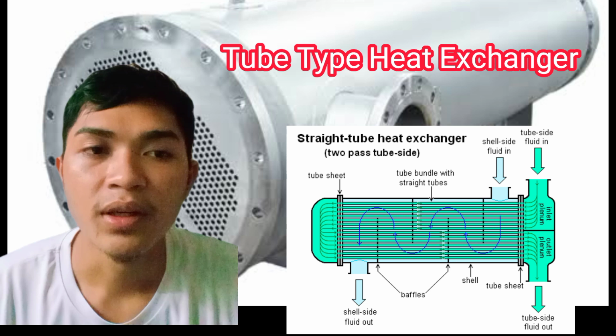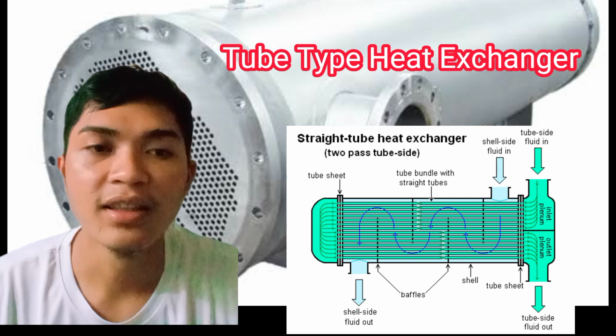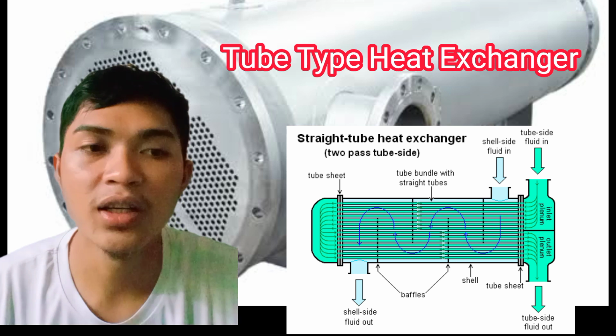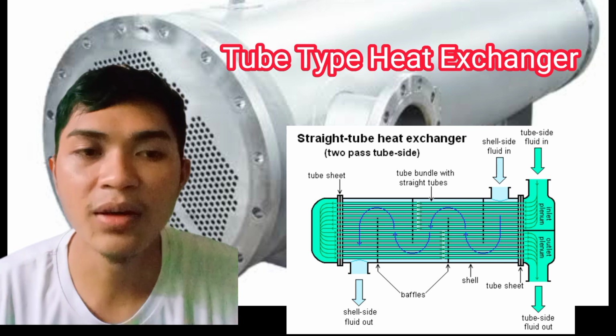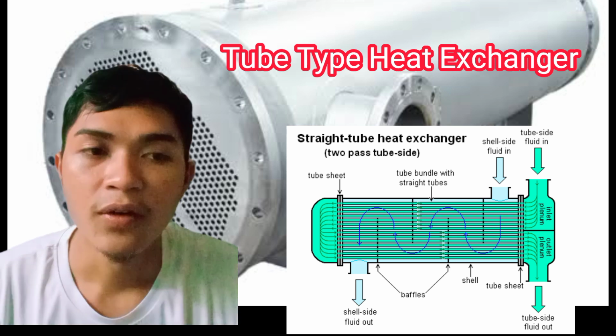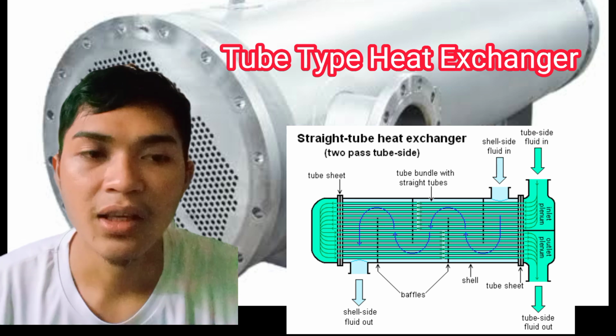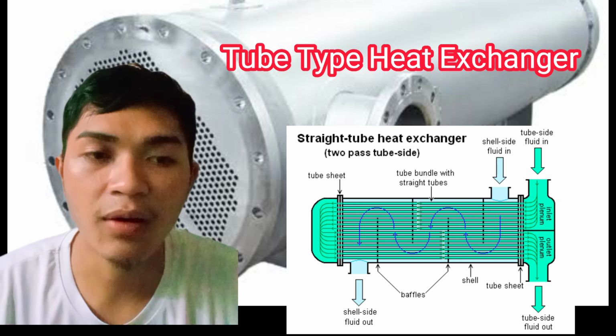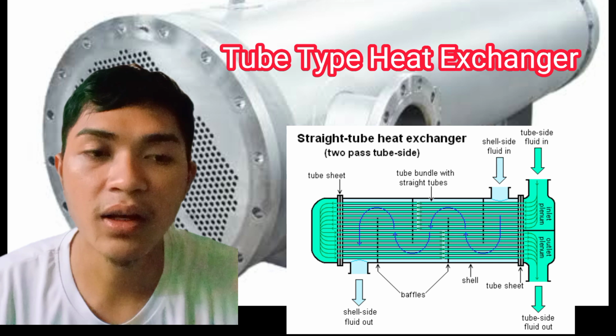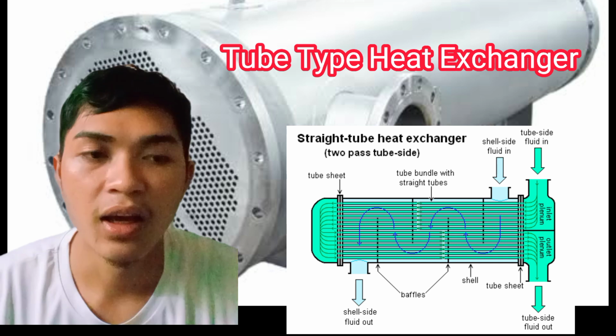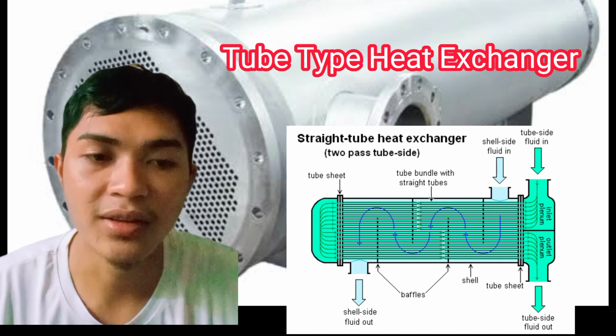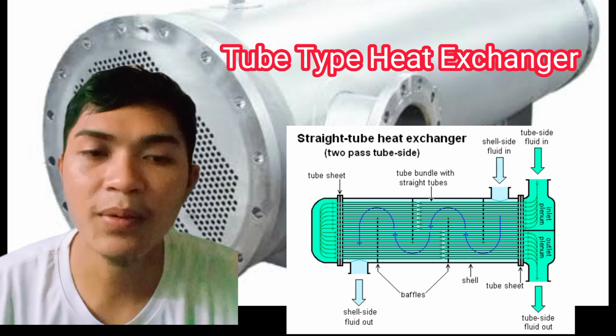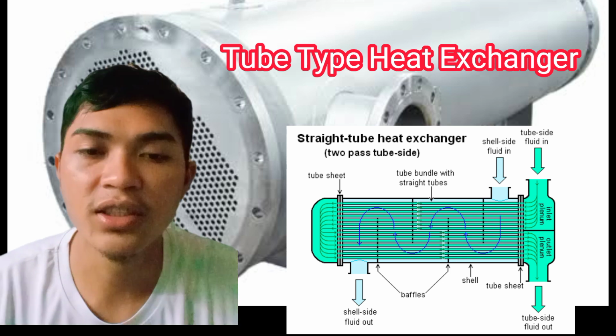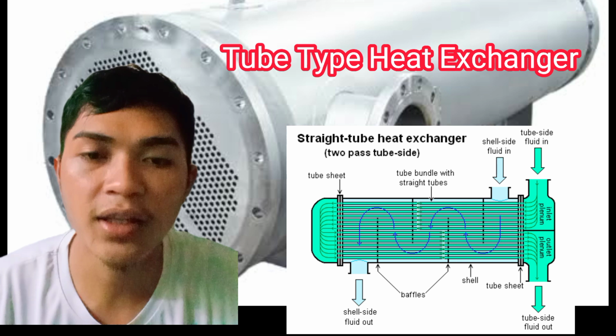Once the cleaning is done, the heat exchanger must be flushed with fresh water to remove any remaining chemical or dirt from the surface. In seawater cooled heat exchangers, anodes are fitted on the cover to protect it from galvanic corrosion. Anodes must be checked and changed if required. Always renew the cover gasket if it is damaged during opening of the heat exchanger.